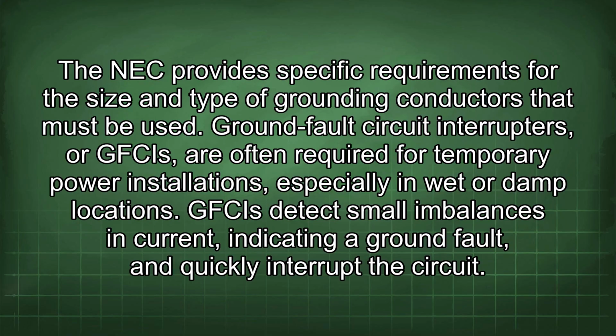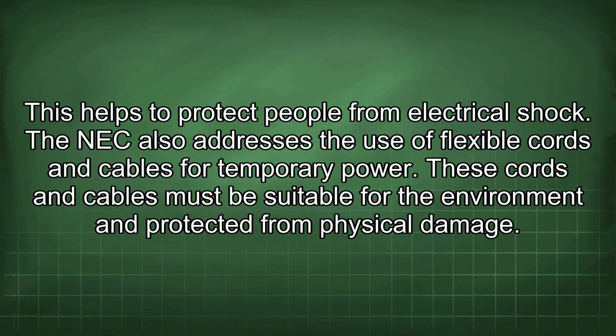Ground fault circuit interrupters, or GFCIs, are often required for temporary power installations, especially in wet or damp locations. GFCIs detect small imbalances in current indicating a ground fault and quickly interrupt the circuit. This helps to protect people from electrical shock.